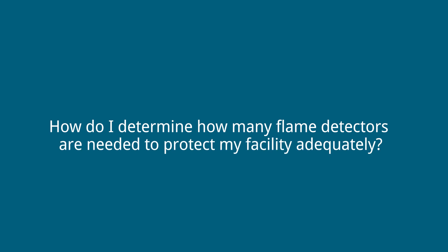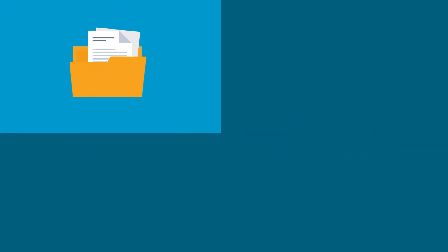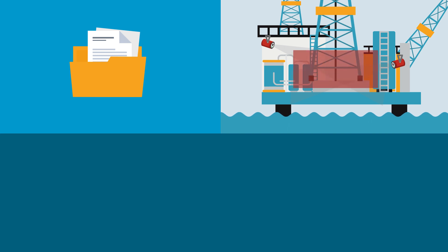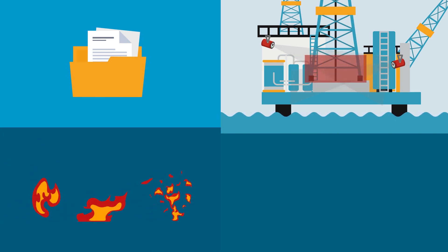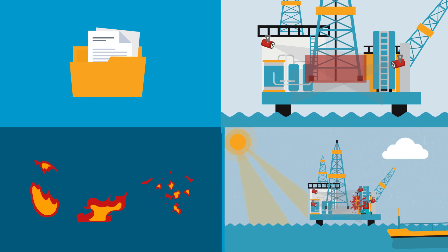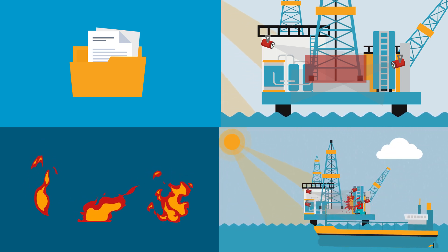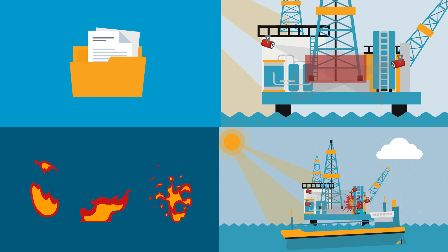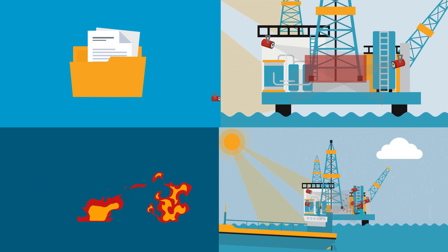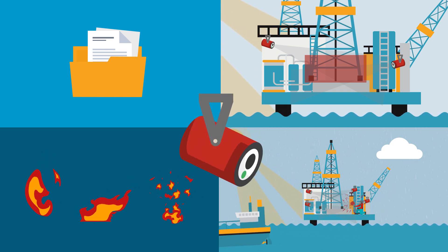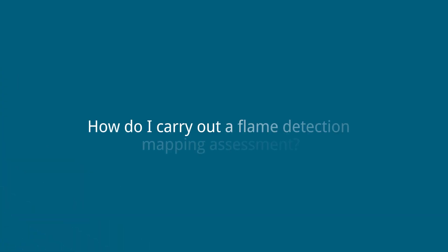We start by needing some basic information: which design standards to use, how large is my fire zone and what can influence it, what are the fire hazards and what detection technology should I select, how do I account for the impact the environment and process have on flame detector performance, and what else determines how many flame detectors I need. How do I carry out a flame detection mapping assessment?